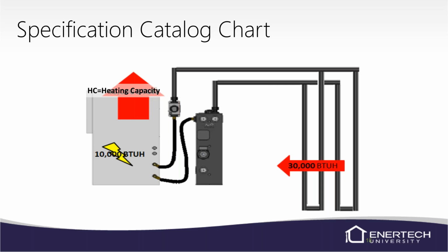Well, in heating mode, we just pick up that heat and we take it into the home. So we've got 30,000 BTUs from the loop field. We've got 10,000 BTUs from the heat of compression. So what we're heating the home with is our total heating capacity, which would be the 30 plus the 10, which would be 40,000 BTUs. That's what we're actually putting into the home. So we can actually figure out what the heat of compression is.